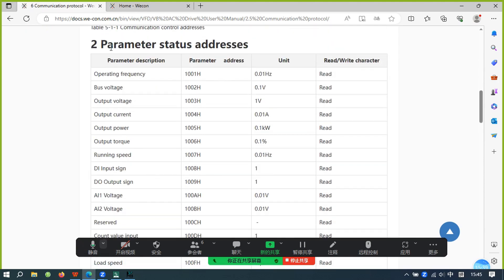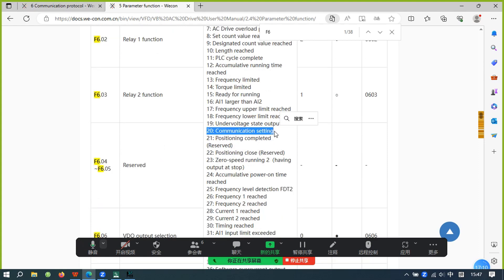This is the parameter state address. The running speed is the actual speed of the motor, and the operating frequency is the output frequency of the inverter — both have the same meaning in VF mode. F6.02 controls the Relay 1 function. If you want to control Relay 1 in the HMI, you need to set this parameter.